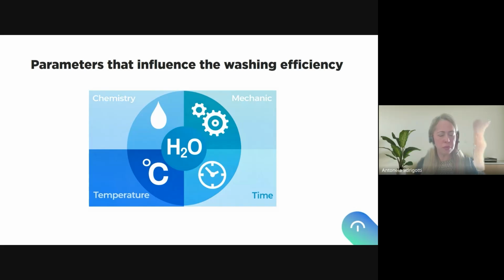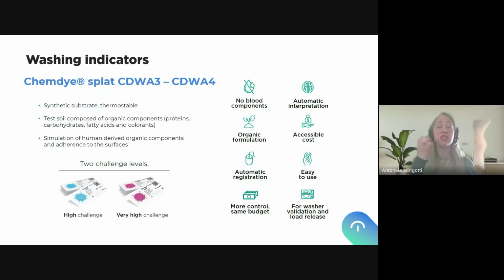So it's very important to keep all the instruments open, disarmed, according to the manufacturer of the medical device, and open to the water spray and the washing process. So what is the solution that we offer to monitor all these parameters? These parameters are integrated, they are not independent. So the success in the end is a very fine tuning between them that will make sure all the instruments will be correctly washed.